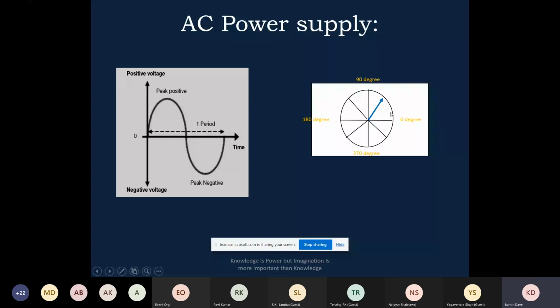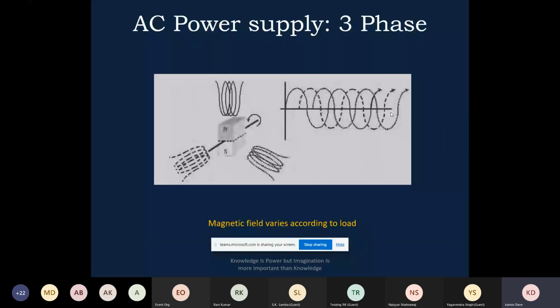If we consider the three phase, then you look at it here, the rotor bars, the north pole is very close to the A phase coil, ABC phase. So the waveform starts from 0 for A phase, then B phase, C phase. The A phase, B phase and C phase are mechanically 120 degree apart. So that is 0 degree, 240 degree, 120 degree, the phasor rotations. This is how the three phase supply is formed.